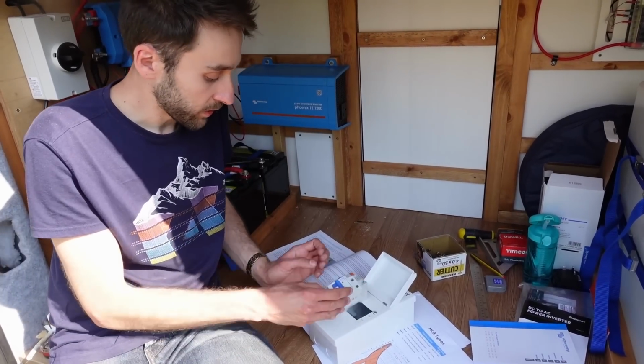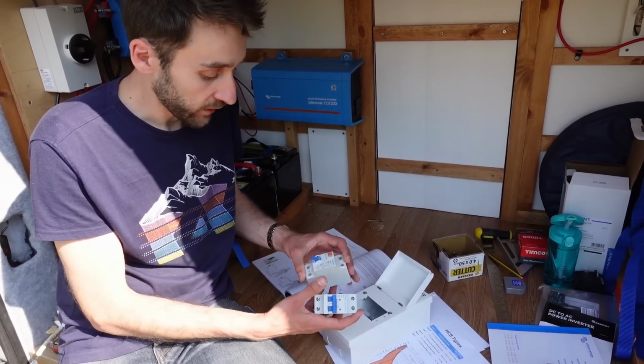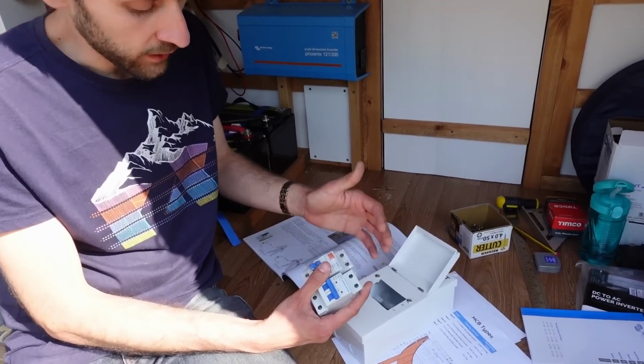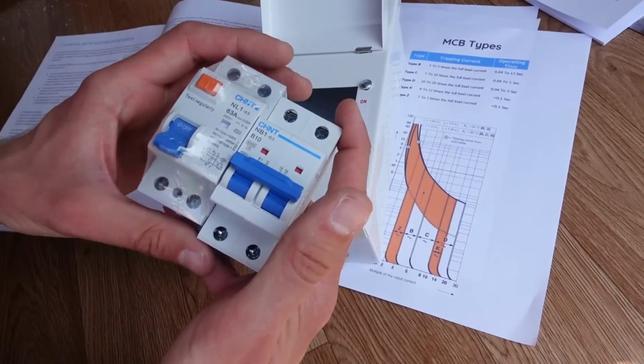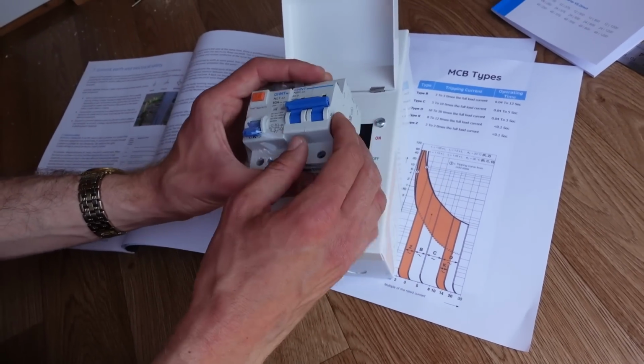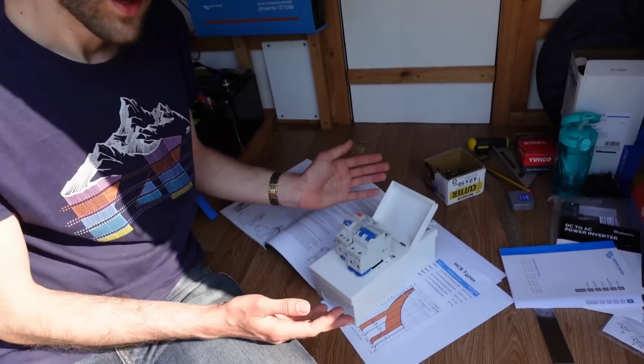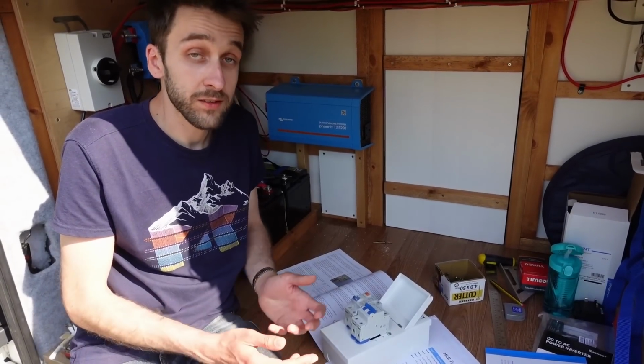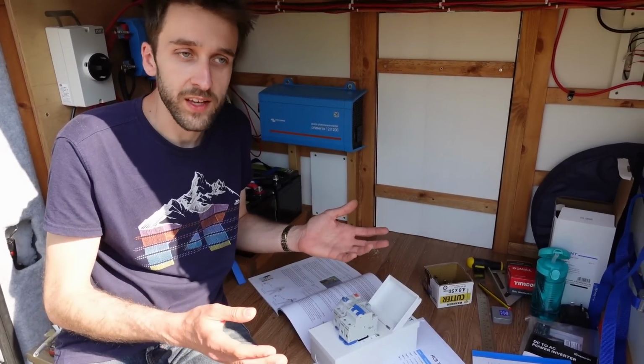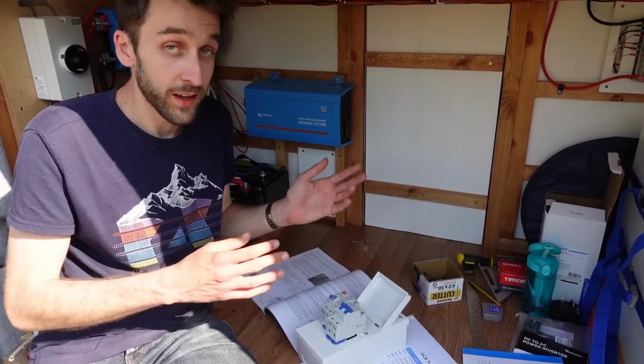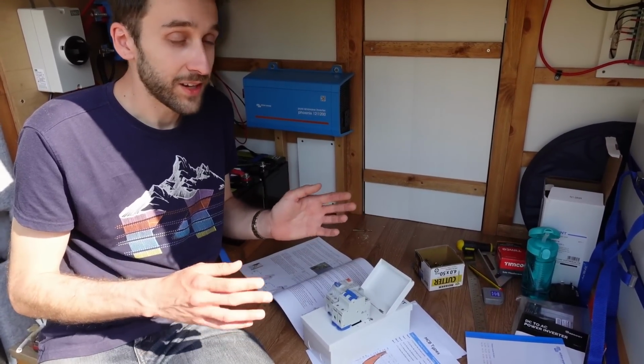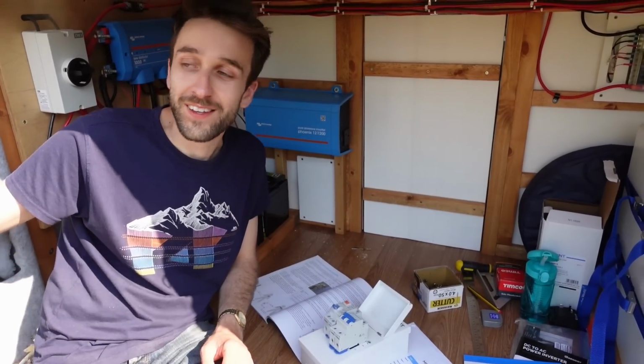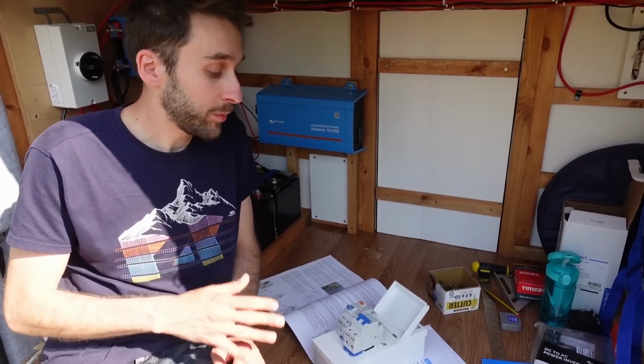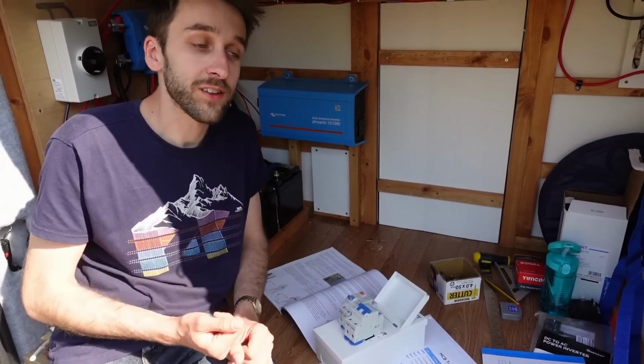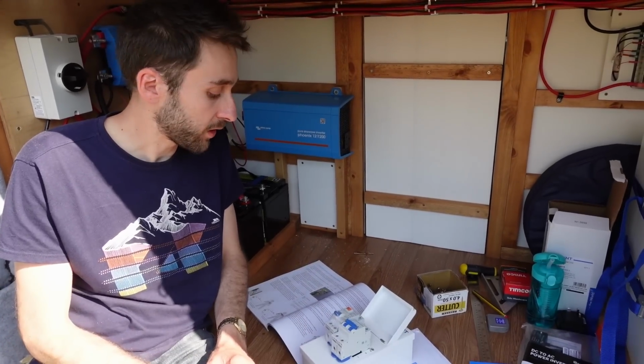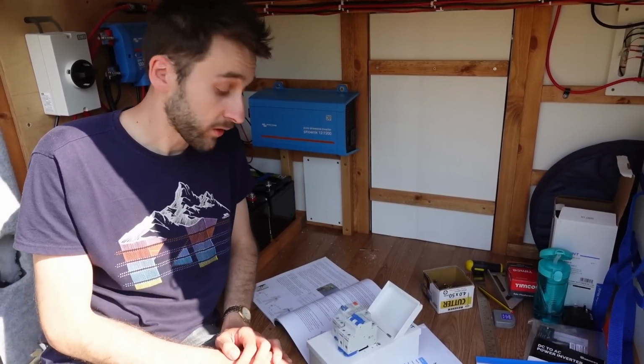And the reason as well, you might have noticed, we've gone for a double pole for both of them. What that means is both of these take the live and the neutral at the same time, so they are actually switching off both wires simultaneously. And in the house you probably wouldn't get that most of the time, but because we're in a camper van, you can get issues, especially if you go to Europe and stuff, where you have potentially the reverse polarity, which means that you might be at some campsite or something and they've got live and neutral the other way around from what you're expecting, and that can cause a lot of problems. For us, it's actually never going to happen like that, because we can't plug into shore power. We don't have that facility, so we don't have to worry about that. But it seemed like it was a good idea, because we're in a camper van, just go with that anyway, and it's better, it's safer. So we've got double isolation switch off on both of those things.